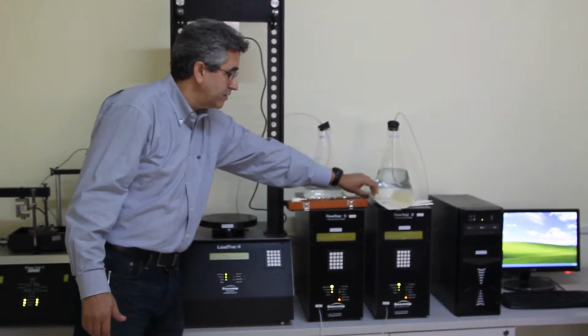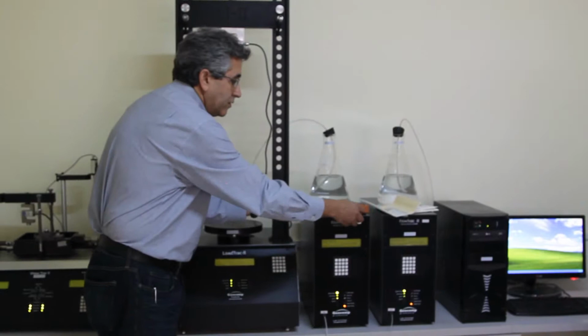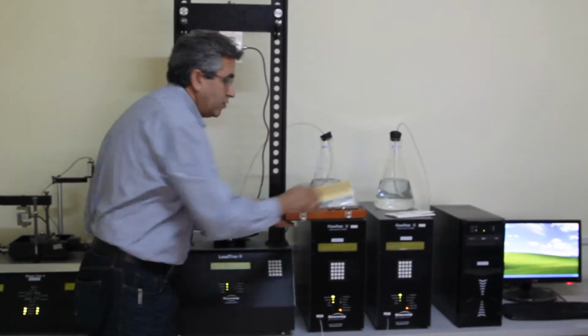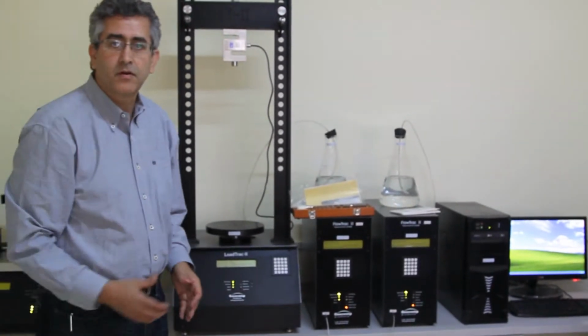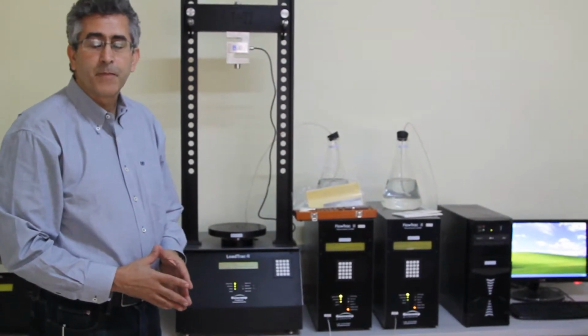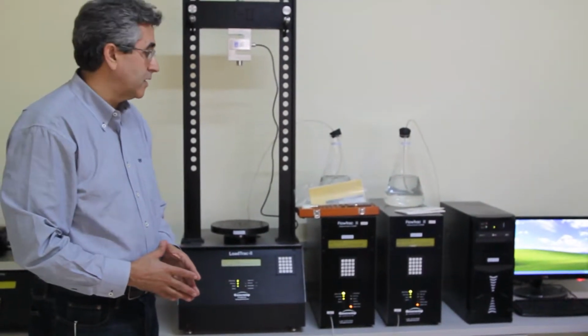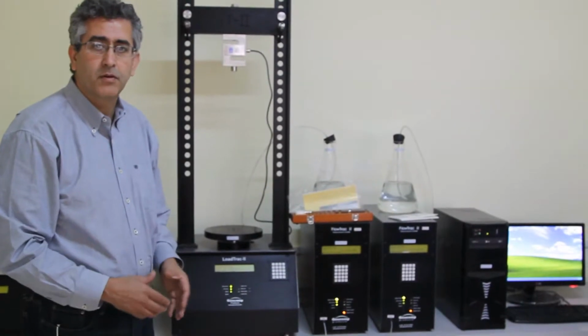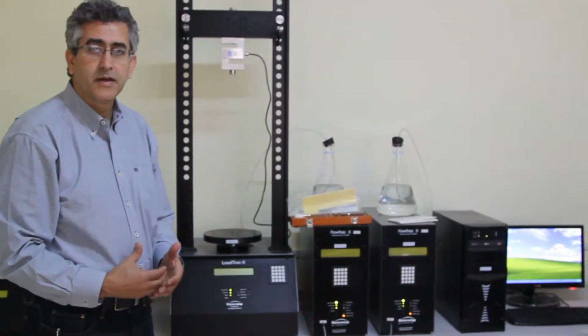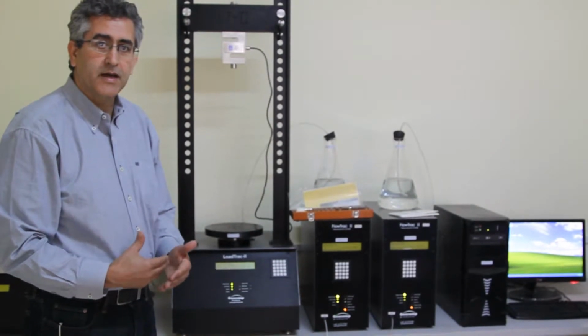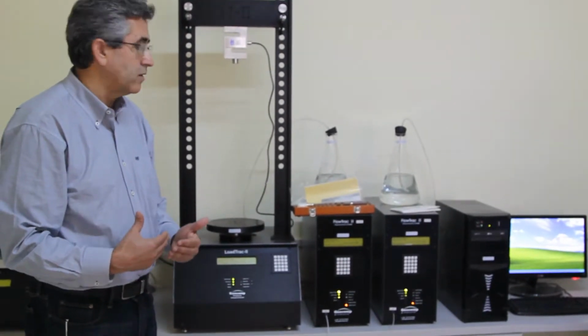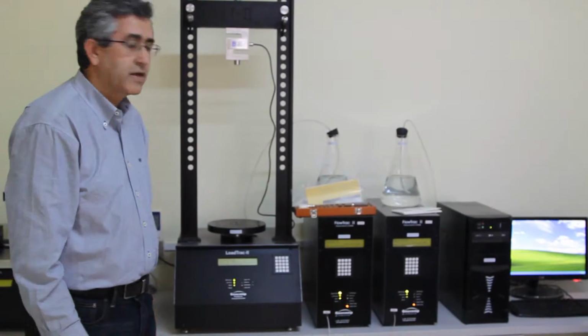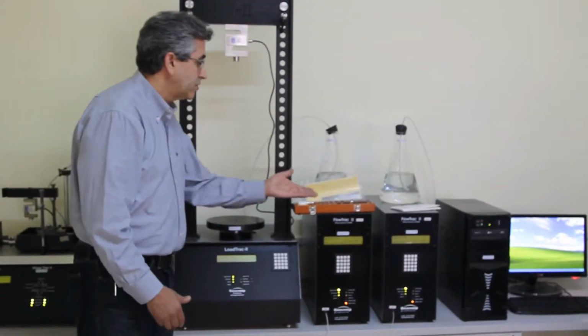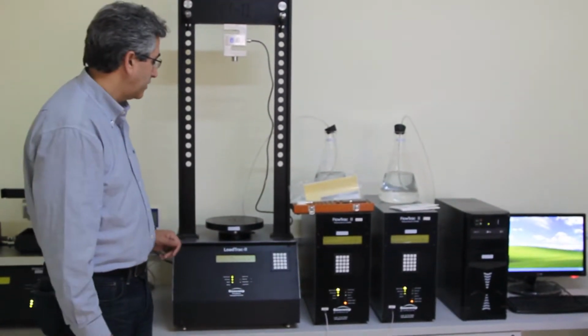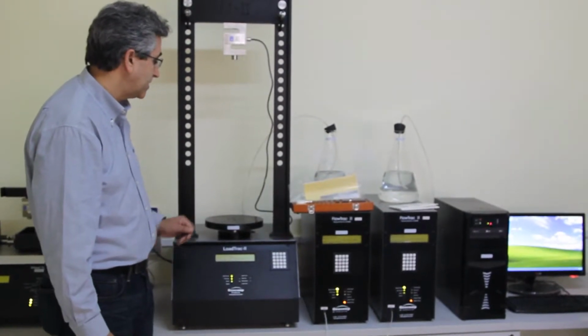This is the calibration that we are going to be using today, and you could have also different references as long as they are traceable. Other people have used micrometers, or you can have a digital dial gauge. As long as they are calibration grade and also traceable, then you can use your calibration reference to do your calibration for your displacement sensor that is underneath the platen here.